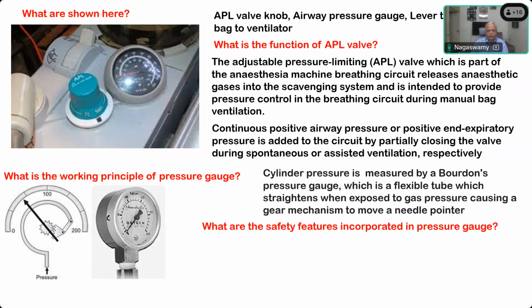Then in some machines you will find there will be an instruction, no oil, no dirt, to prevent explosion. And of course, as you said, the backside is made up of thin material, and any increase in pressure and damage, it will rupture only on the backside without causing any damage to the anesthetist or the patient.